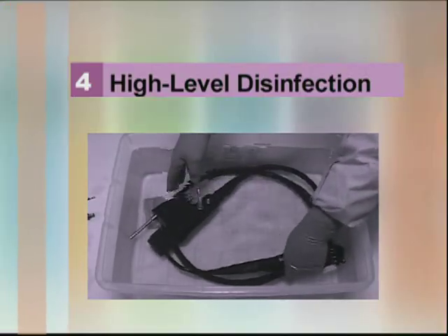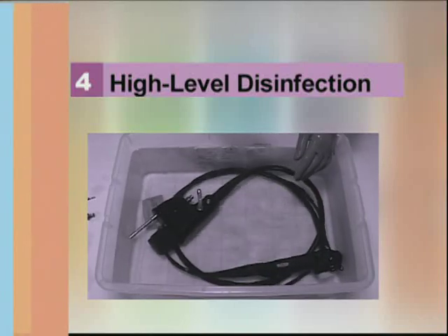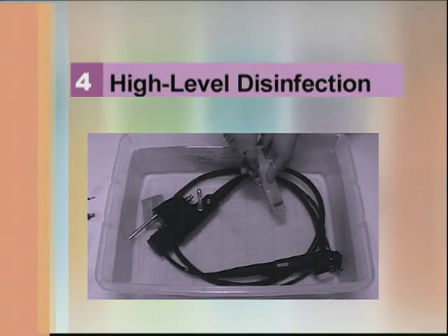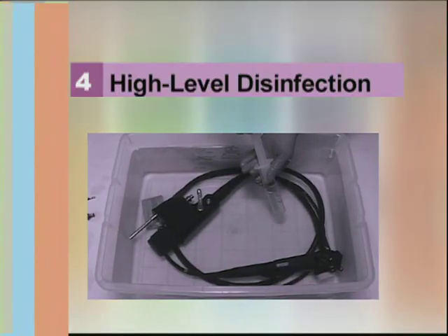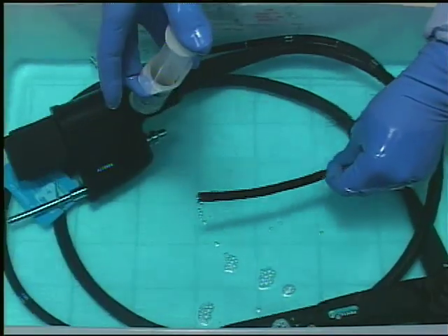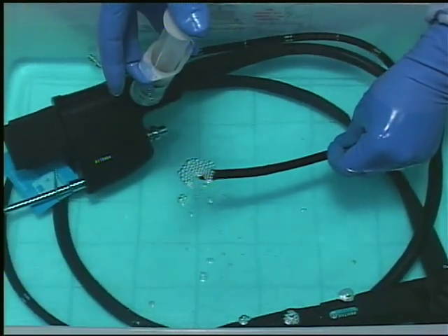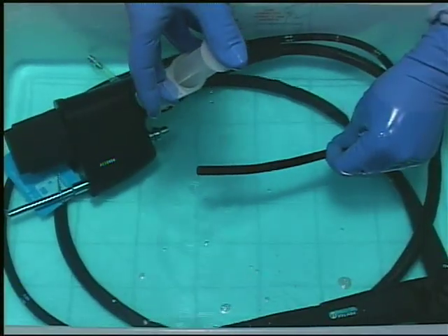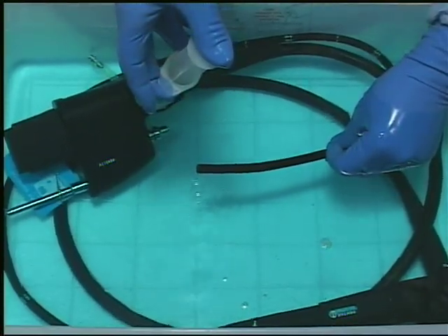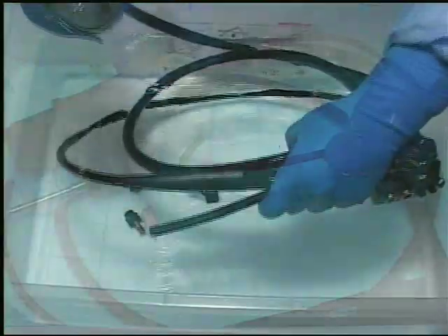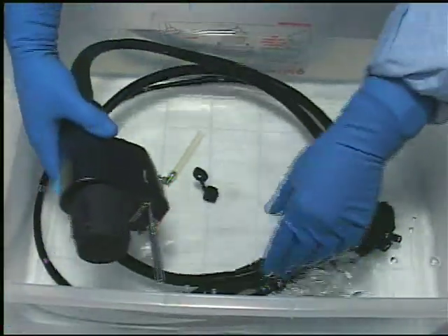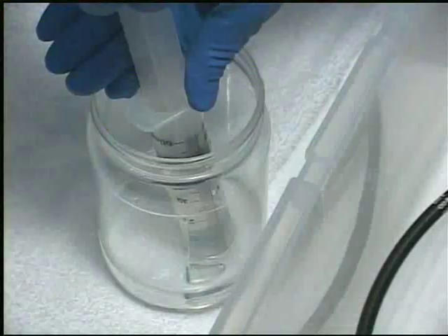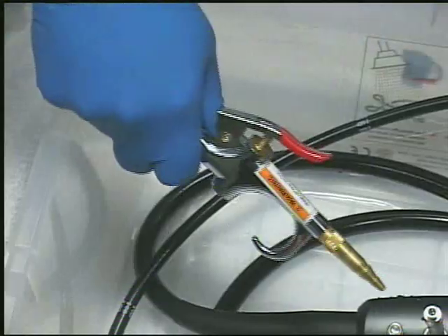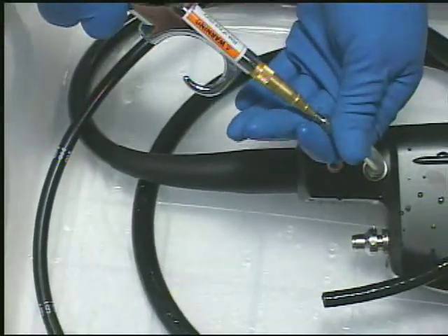High-level disinfection should be performed in a decontamination area. It is imperative that one ensures contact of all internal and external endoscope surfaces with a legally marketed high-level disinfectant sterilant. Disinfection goals: to remove, inactivate, or kill pathogenic microorganisms which may remain on an instrument after cleaning to render it patient-safe for subsequent use. After high-level disinfection, a water rinse is required to remove residual disinfectant. A final alcohol rinse followed by forced air should then be applied to thoroughly dry instrument surfaces.